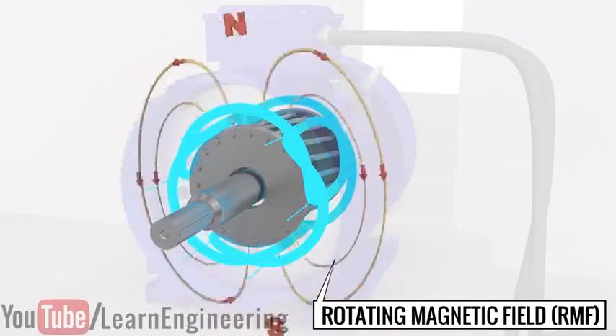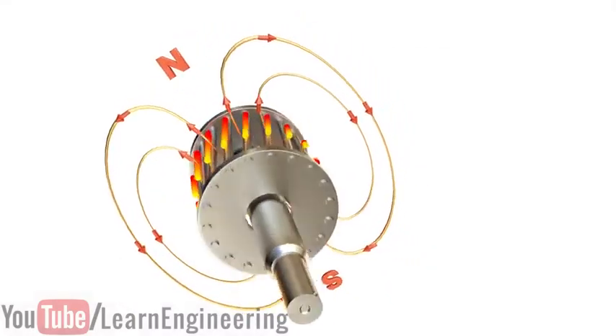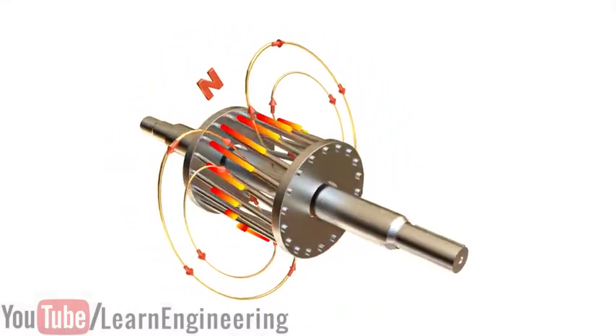This RMF cuts the rotor bars. According to Faraday's law of electromagnetic induction, an electromotive force is induced in the bars. Because the rotor bars are short-circuited by the end rings, this induced EMF generates a current to flow through the rotor bars.